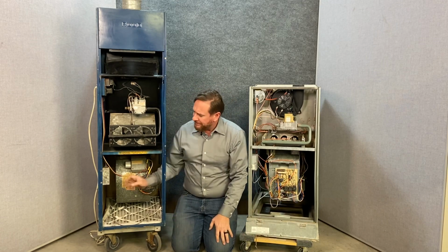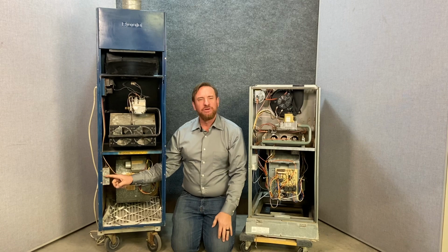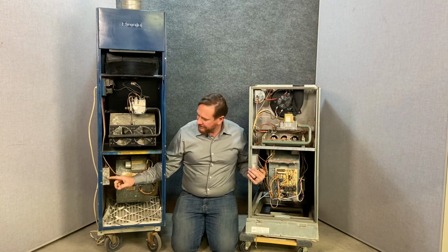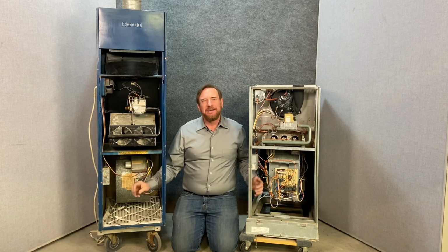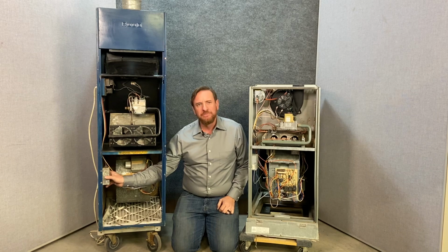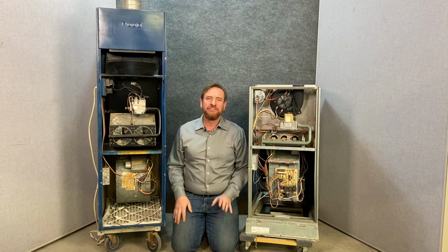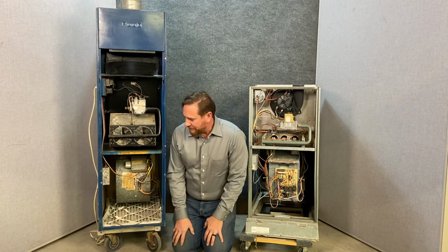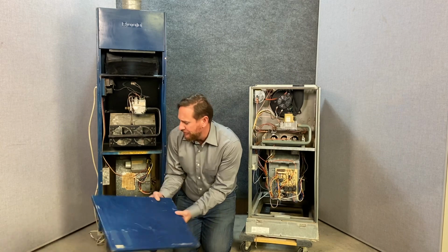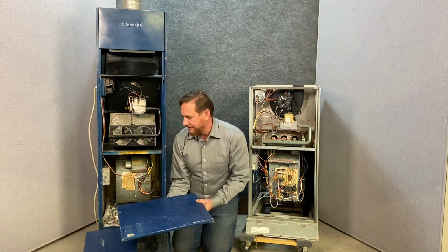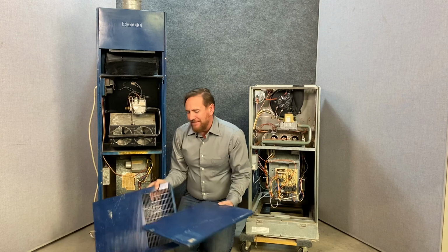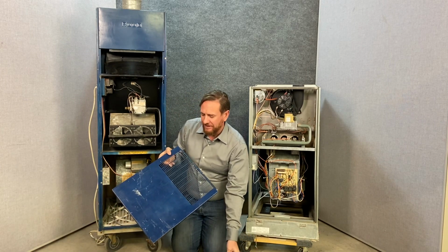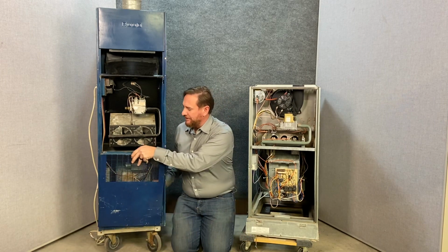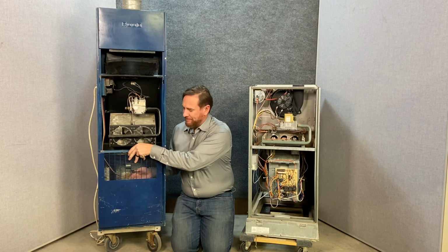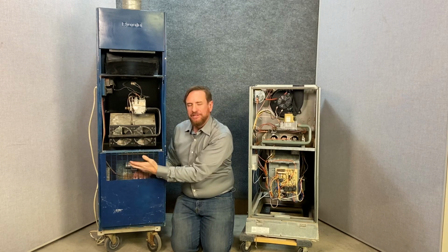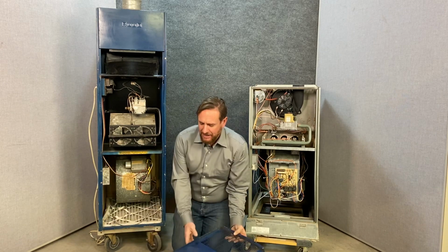So both of these systems have a door interlock or a door safety switch. This one is here and this one is here. That's a very important aspect, because when this door comes off, it shuts the power off to the furnace, so it will not run. Why that's important is because some customers will take this door off to get to the filter. So if they don't understand how the doors work and they try to put the wrong door back on, it won't let the switch push in. This keeps them safe, so it's not pulling combustion air into the unit.